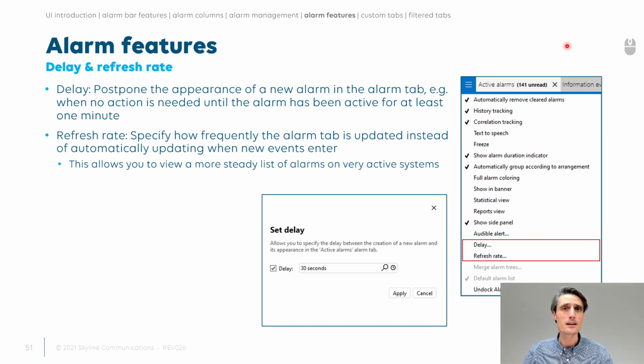And typically they say, yeah, but that can happen. You don't worry about those alarms that only pop up for 10 seconds. Whenever it's more like, let's say, more than 30 seconds, then you can take action. Yeah, but then I continuously have to look at all those alarms that are only happening for a few seconds, and I need to check my clock, things like that. Well, actually, you can embed this procedure into your DataMiner system by activating the delay option.